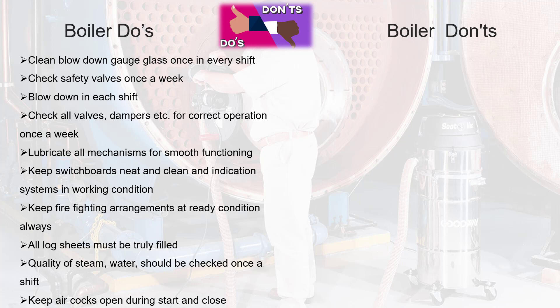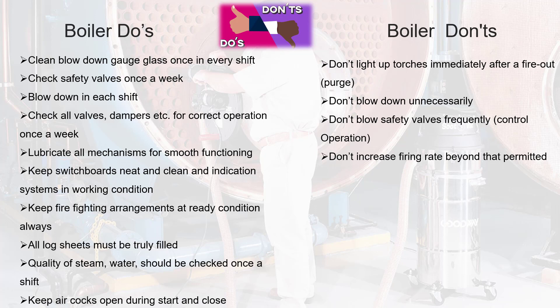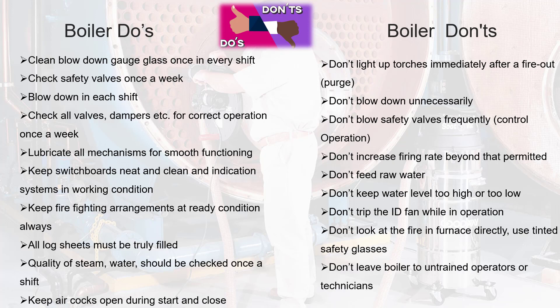Boiler DON'Ts: don't light up torches immediately after a fire out — purge first. Don't blow down unnecessarily. Don't blow safety valves frequently — control operation. Don't increase the firing rate beyond that permitted. Don't feed raw water. Don't keep the water level too high or too low. Don't trip the ID fan while in operation. Don't look at the fire in the furnace directly — use tinted safety glasses. Don't leave the boiler to untrained operators or technicians.